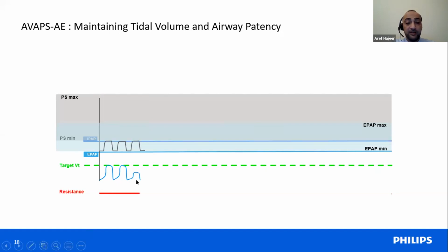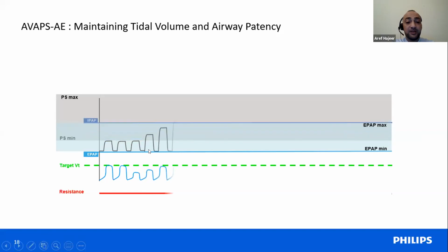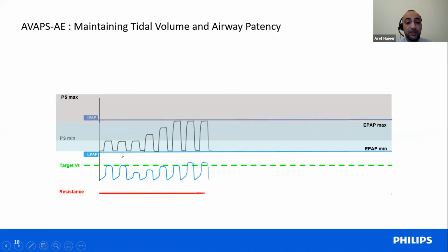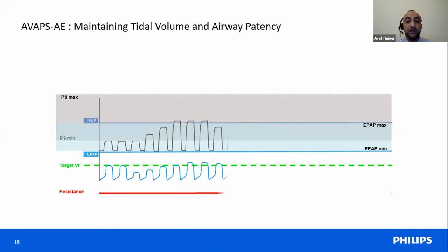Then suddenly the device finds a drop in tidal volume, for example, and we expect the device to start to increase the IPAP at that time, because there is no increase in the resistance. And this is what the device did. It kept the EPAP at the minimal value and increased the IPAP only. Then the tidal volume of the patient went back to normal. Then the device will start to go back to the minimal pressures, as I mentioned before.